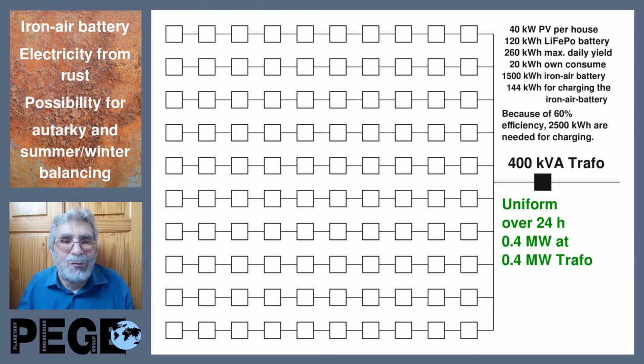And now we try it with the iron-air battery in addition. We have the same per house, but in addition we install 1,500 kilowatt hours of iron-air batteries, and because they have only 60% efficiency, we need 2,500 kilowatt hours to charge them. And then we have again this maximum yield day, where our photovoltaic delivers 260 kilowatt hours.